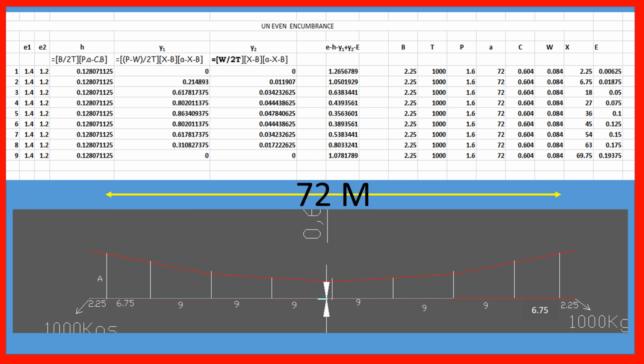Even where the encumbrance is changing, where we are approaching a tunnel, an overland structure, or a foot-over bridge, we are reducing the OHE height and the encumbrance to permit. But keep it in your mind, the minimum encumbrance must be 300 millimeter, and the midspan dropper should not be less than 150 millimeter.